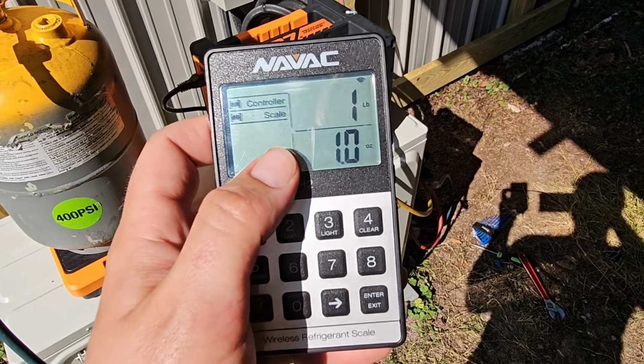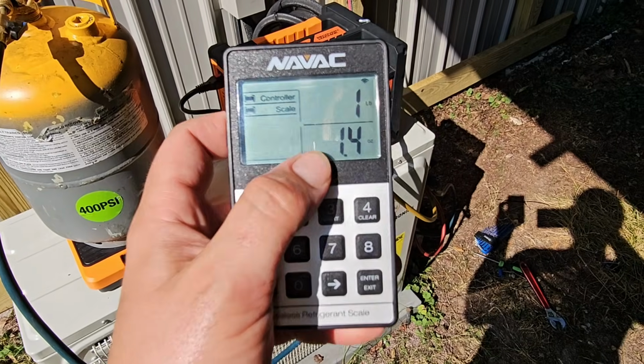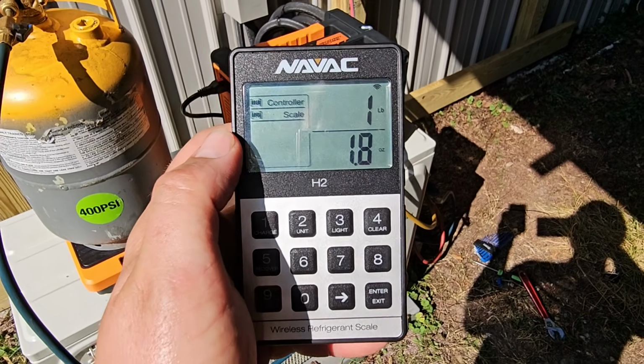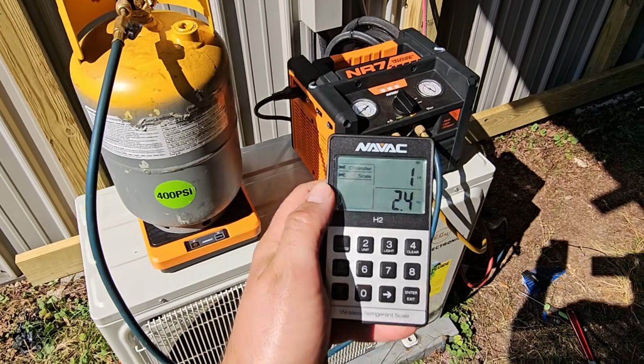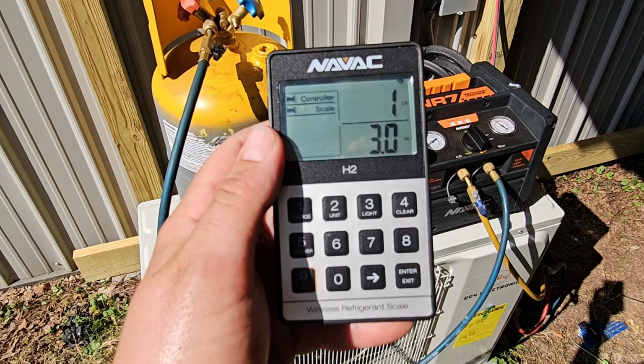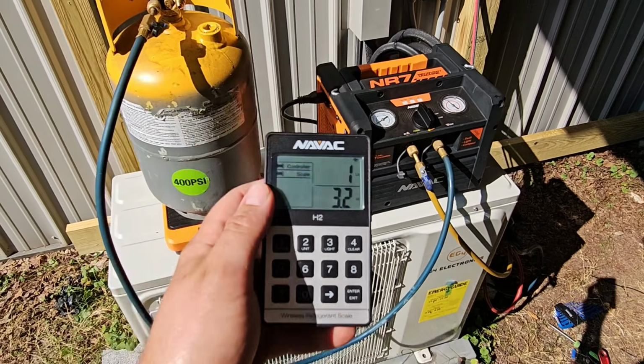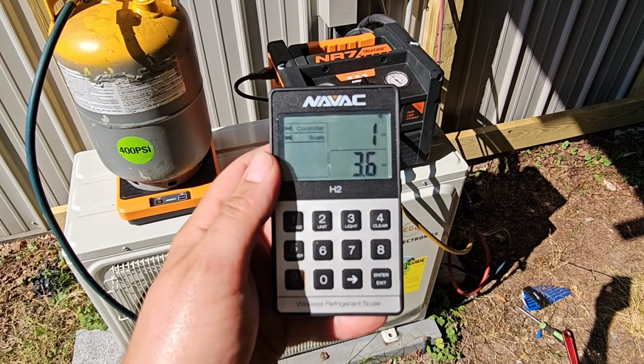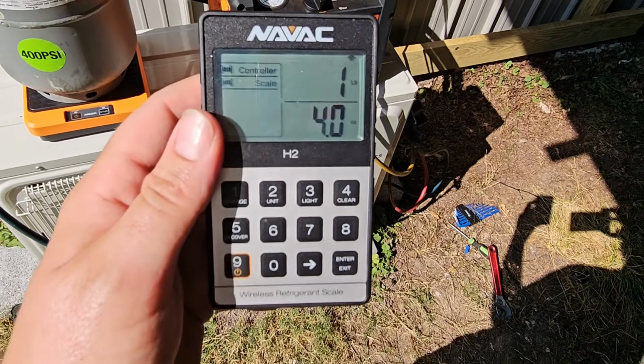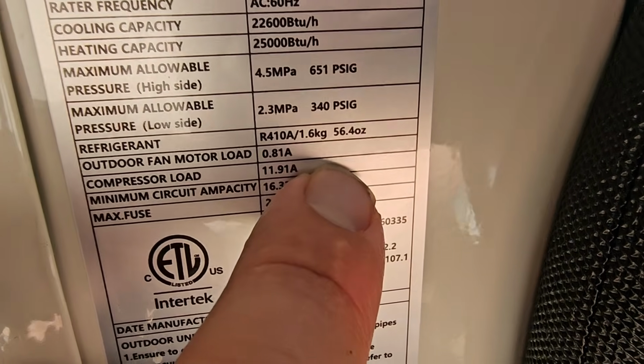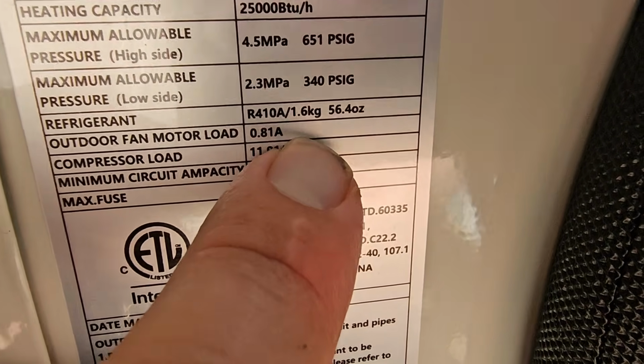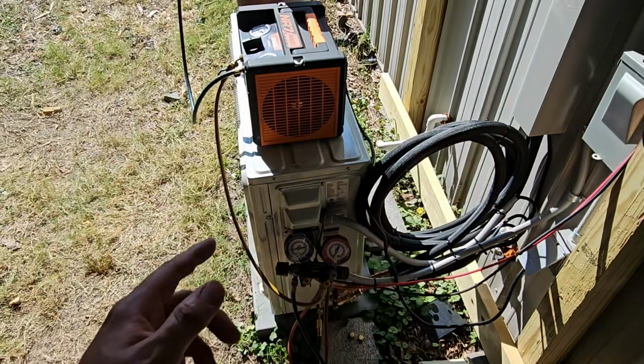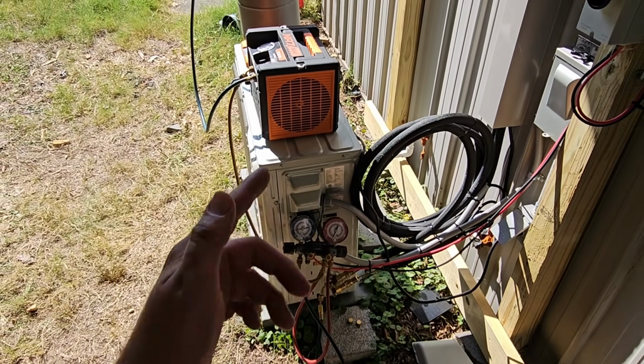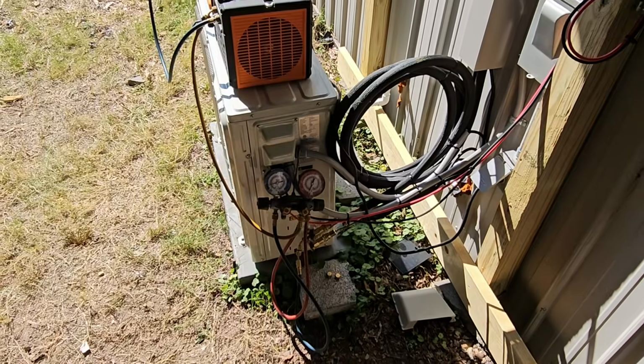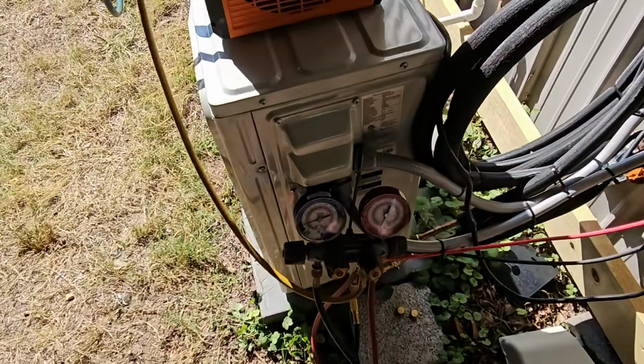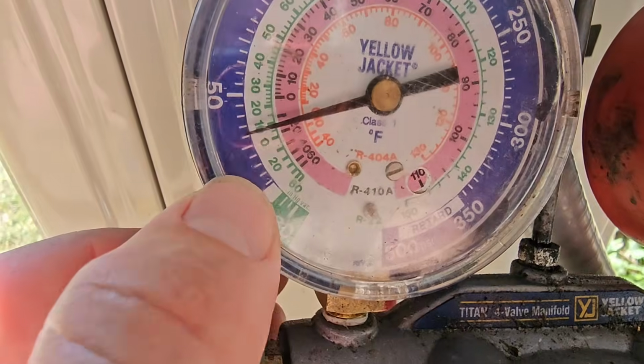Now if you look at the remote for the scales, you can see how the pounds are increasing, the ounces are increasing, and we're actively recovering the refrigerant from the system into the tank. And I'm timing this to see how long it takes to recover the refrigerant out of a mini split. Now let's look at how many pounds this holds. Looks like it holds 410A, 56.4 ounces, or 1.6 kilograms. So this system, if you divide 56 by 16, you'll see it holds 3.5, so about 3.5 pounds. Now if you look, it's almost down to 25 PSI.